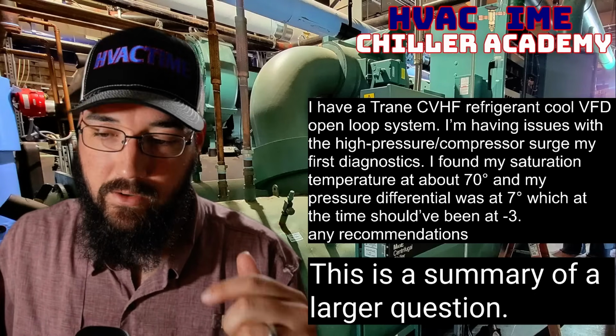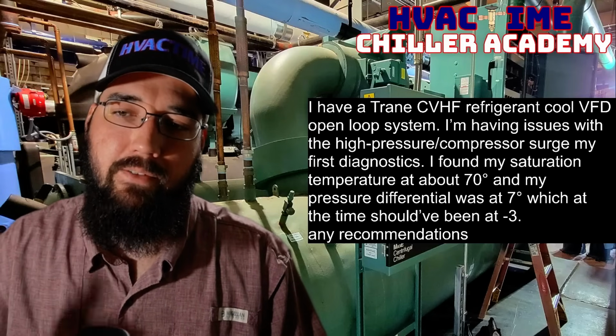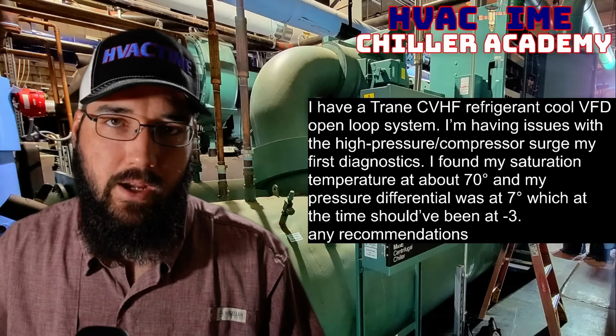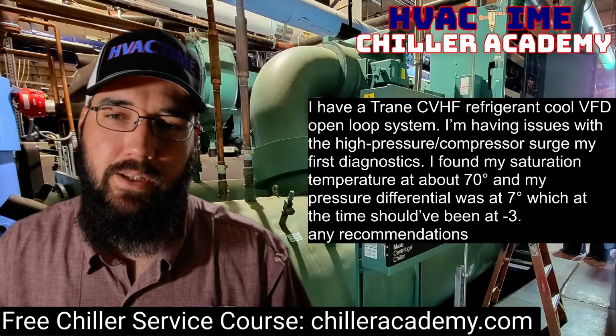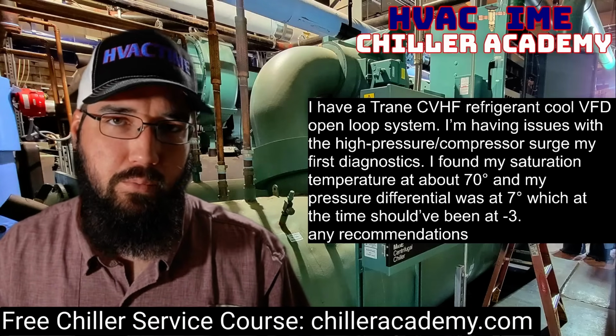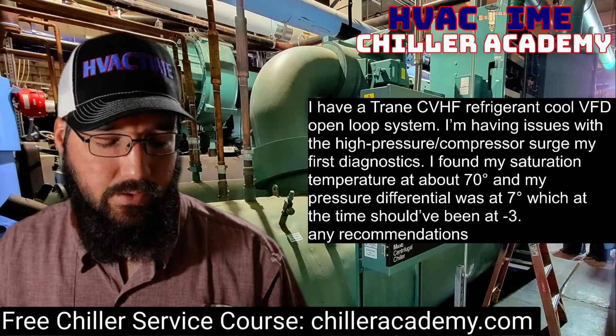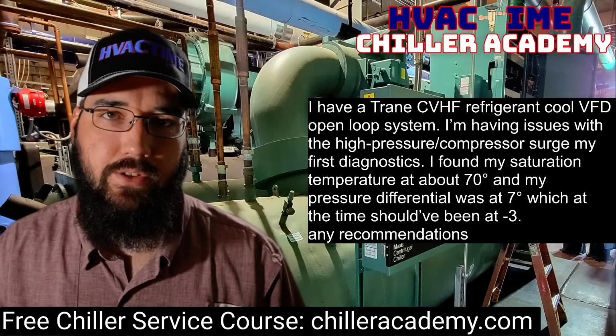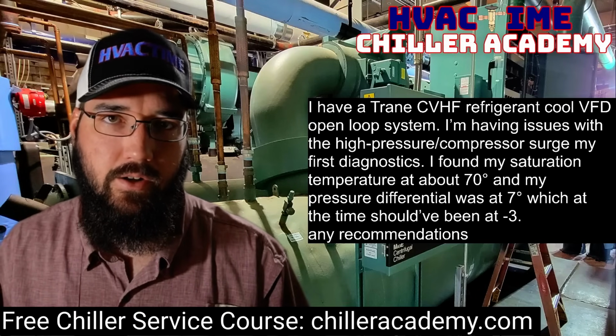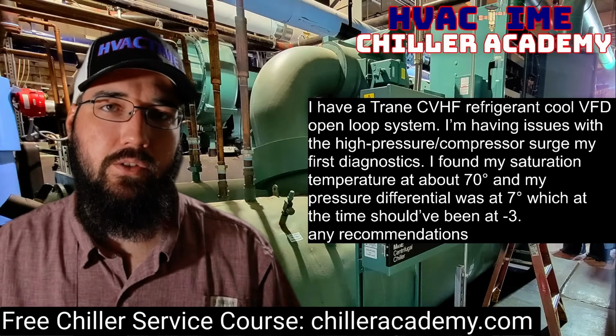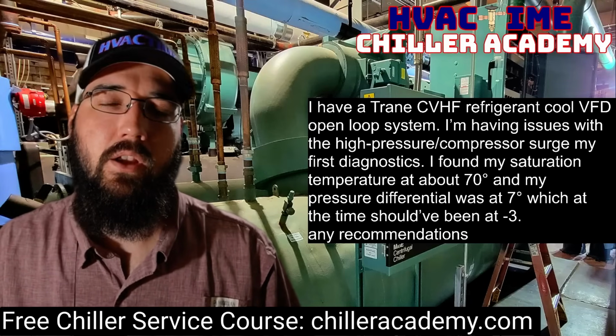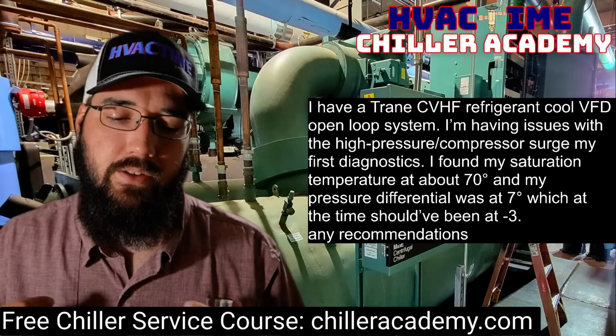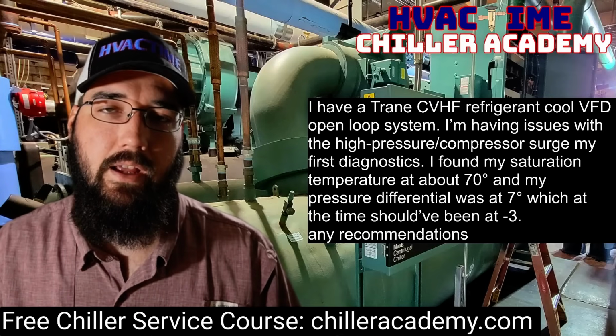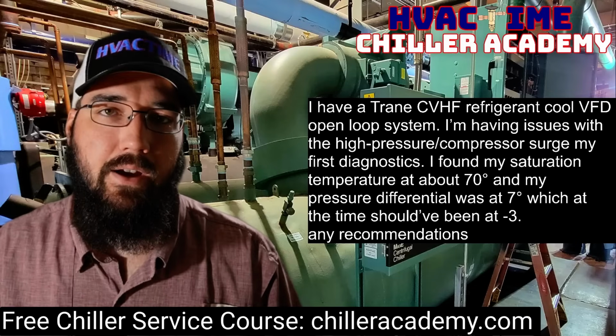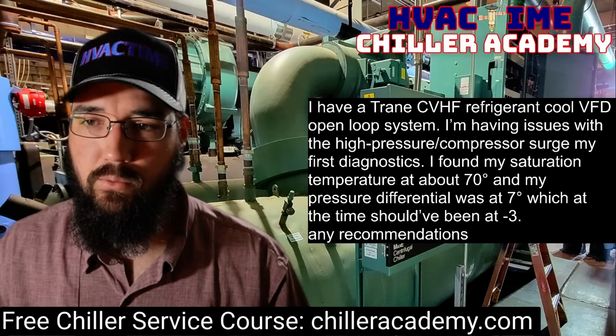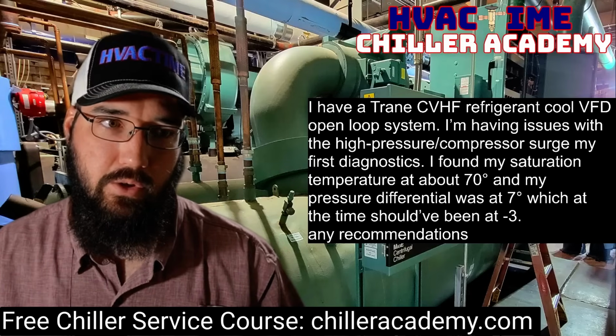There is a lot of air in the system. You've got a CVHF, you're having trouble with it, dealing with high pressure and surge. The pumps were in hand, it sounds like. You put them in auto, and so let's pause there first. I would be cautious defaulting to putting drives in auto if I don't already know what's driving the auto piece of it. One of the things to keep in mind is the automation system may be struggling, and you may not have a system that needs a variable loop. You may not have a variable flow setup.